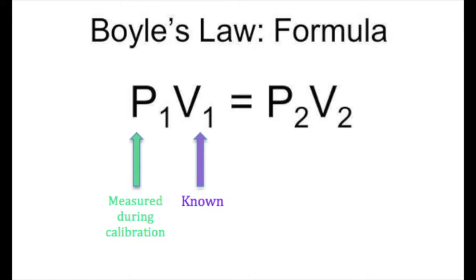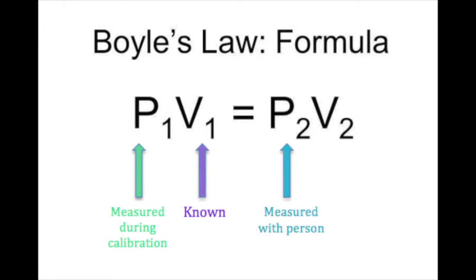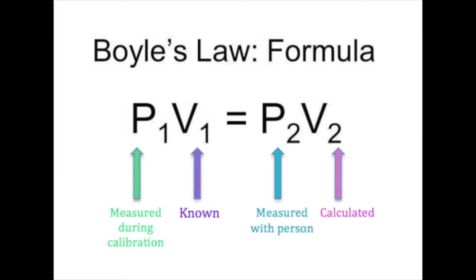Since the Bod Pod already took measurements of baseline pressure and volume, which are P1 and V1 in our base equation, and now has a measurement of the pressure in the chamber with the subject sitting inside the chamber, which is P2, a quick rearrangement of Boyle's Law gives a result for the volume of the subject, which is V2.